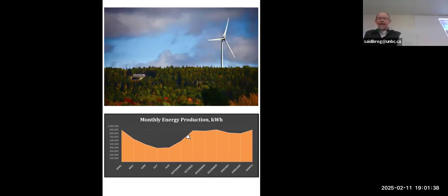And you know what this tells me? It tells me these turbines have been well selected, because if you extended this curve upward, that would show what the turbines would generate if they did not have a governor preventing them from turning past a certain RPM when the wind is high in the winter. But by selecting turbines in this range, the summer production is quite high as well.